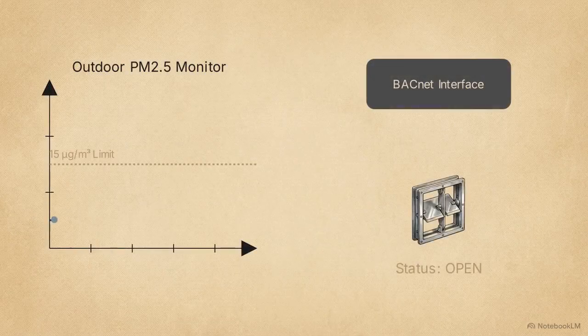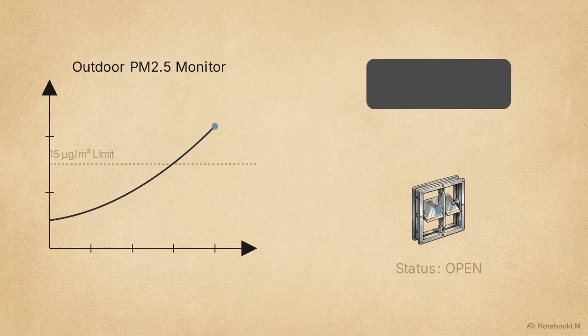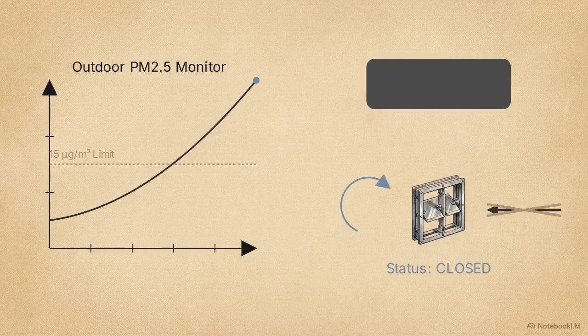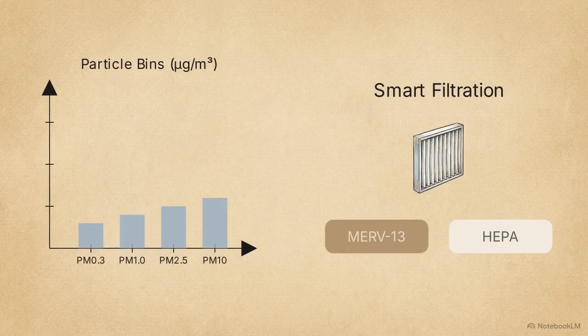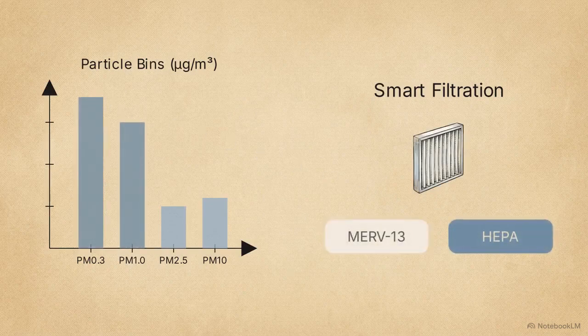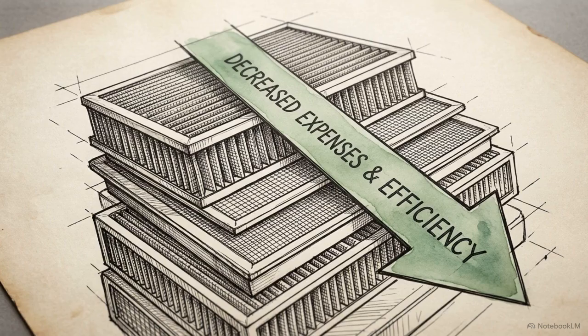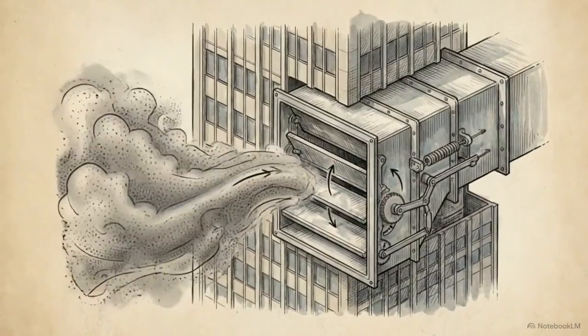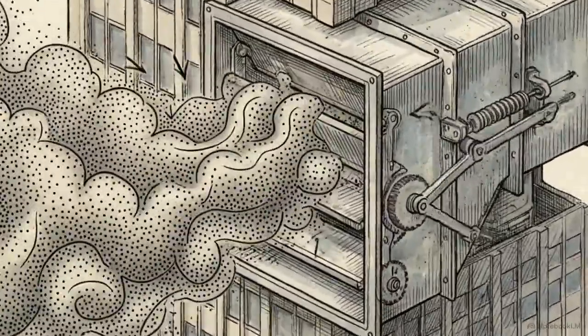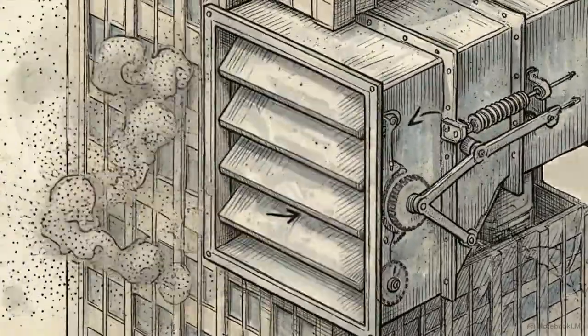This graphic illustrates a live trigger event. If street-level PM 2.5 crosses 15 micrograms per cubic meter, the interface signals the BACnet system, the standard data communication protocol for building automation, to physically close the intake dampers. Granular data parsing also drives a smart filtration strategy, toggling between MERV13 and HEPA filters, depending on the specific particle bin sizes detected outside. This precise optimization reduces premature filter replacement costs by 20 to 30%. The building evolves from a static shelter into an active, closed-loop machine, responding dynamically to its local atmosphere.